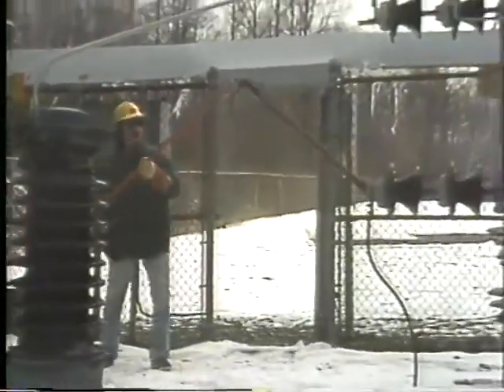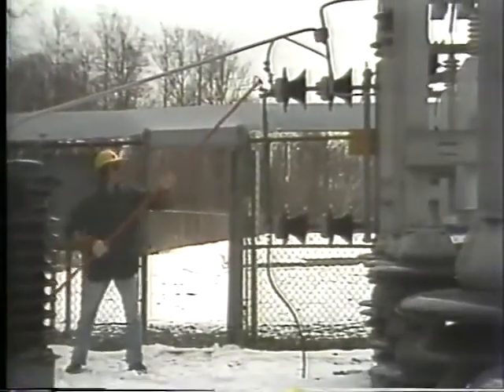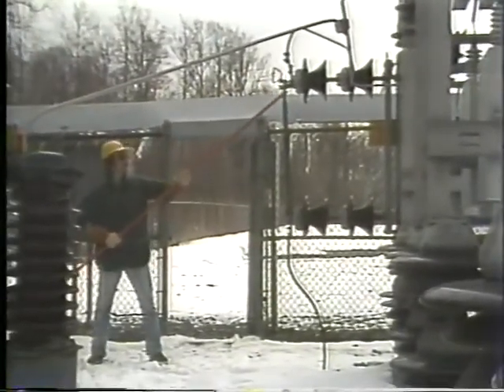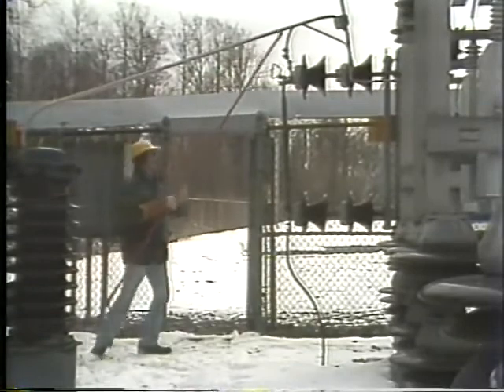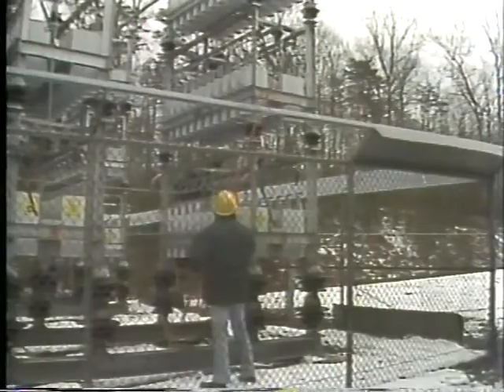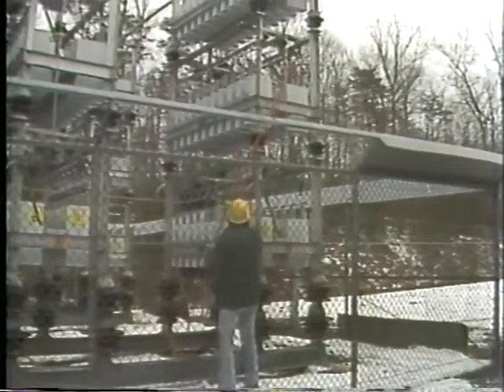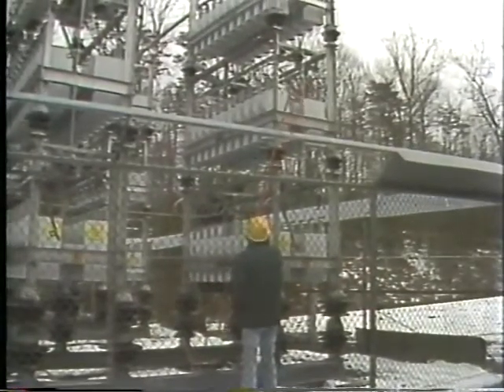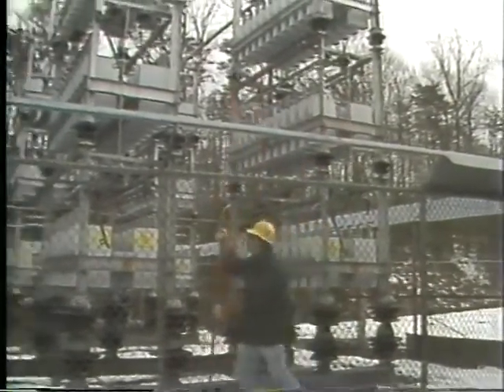Using an insulated pole called a hot stick, he closes the ground switch. In this case, the frame of the capacitor bank is one of its main terminals. Now that the frame is grounded, he can short out each row of capacitors one at a time. Shorting the capacitors to the frame means that any remaining voltage discharges to the frame and from there into the ground.